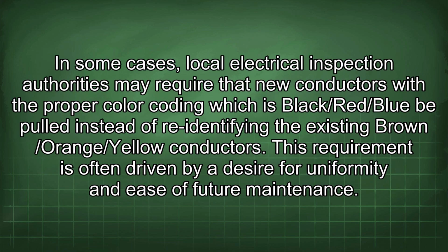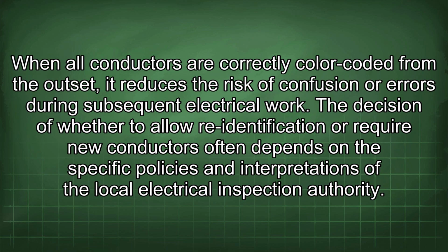In some cases, local electrical inspection authorities may require that new conductors with the proper color coding, which is black/red/blue, be pulled instead of re-identifying the existing brown/orange/yellow conductors. This requirement is often driven by a desire for uniformity and ease of future maintenance. When all conductors are correctly color-coded from the outset, it reduces the risk of confusion or errors during subsequent electrical work. The decision of whether to allow re-identification or require new conductors often depends on the specific policies and interpretations of the local electrical inspection authority.